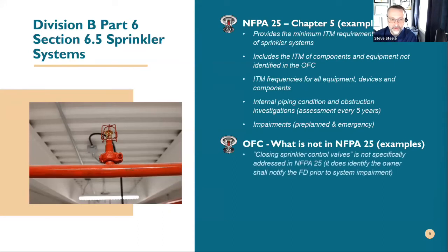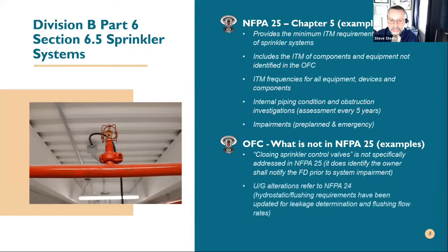As for what is not in there for sprinkler systems, one thing I identified is the closing of the sprinkler valve in a fire scenario. The OFC clearly identifies that you're not to close the valve, as it may affect things if somebody closes it too early, for obvious reasons. It's not specified in 25 the same way, but 25 does identify that an owner or anybody other than the fire department shall not close or impair a system. Even though it seems obvious, in a fire scenario it's no different than if it was a Monday with no fire—you cannot touch it without notifying the fire department. So there's some necessary language to look at for that process, even if not the exact wording.